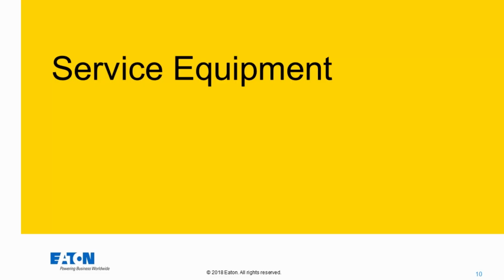Okay, I certainly know that they're not allowed to modify the equipment. For instance, if you had a piece of equipment that didn't have the proper short circuit current rating, and it was possible to modify that equipment so that you did have a proper SCCR, you wouldn't be able to do that. A manufacturer couldn't come out there and then just relabel the equipment. So that is one thing I know would not be permitted, but I think you're right in this scenario.